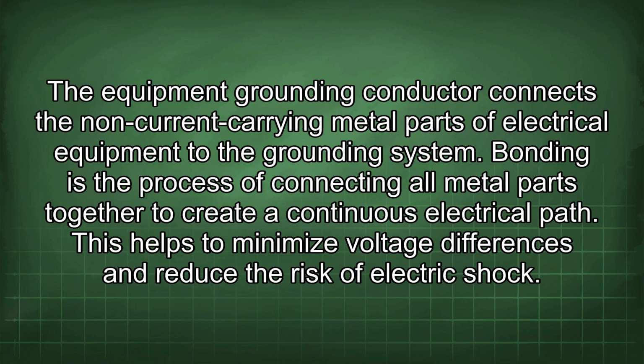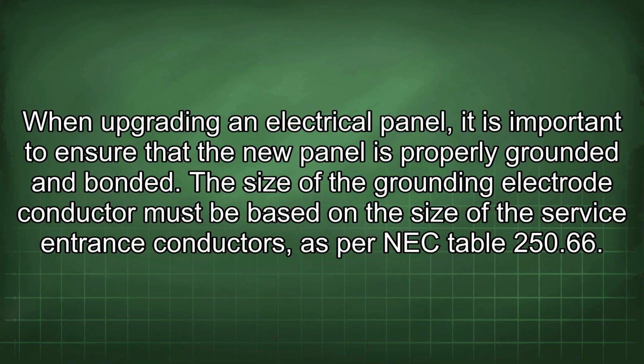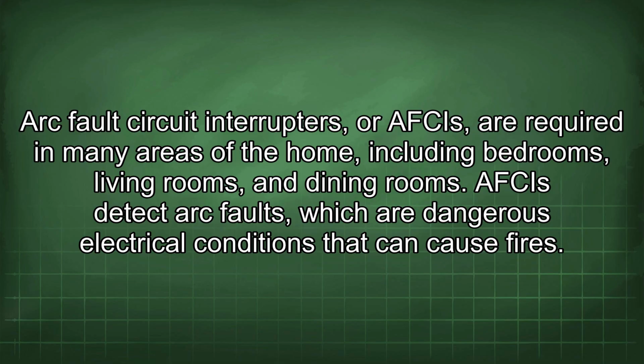Bonding is the process of connecting all metal parts together to create a continuous electrical path. This helps to minimize voltage differences and reduce the risk of electric shock. When upgrading an electrical panel, it is important to ensure that the new panel is properly grounded and bonded. The size of the grounding electrode conductor must be based on the size of the service entrance conductors, as per NEC Table 250.66.